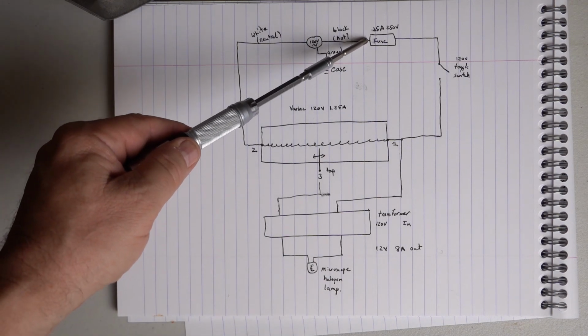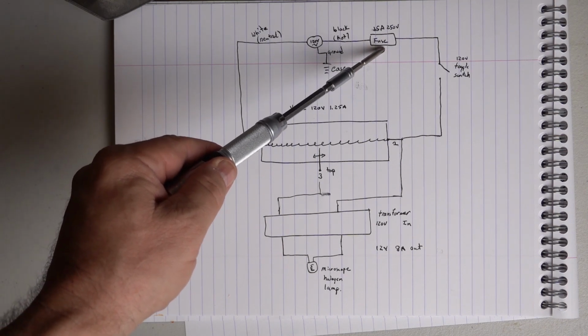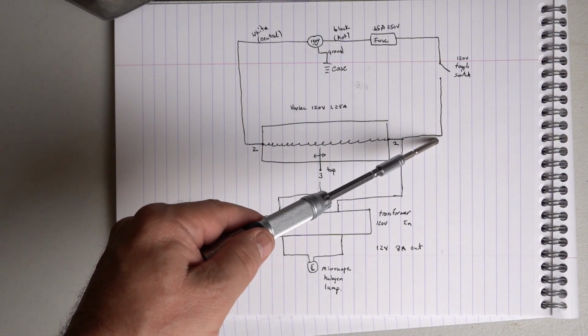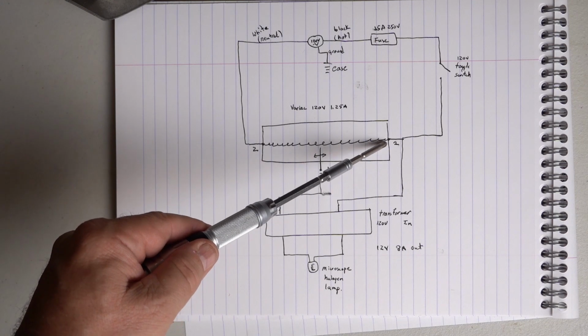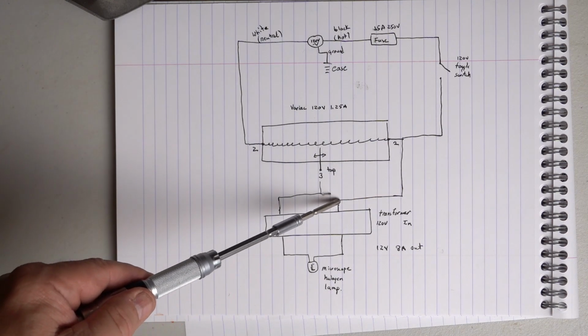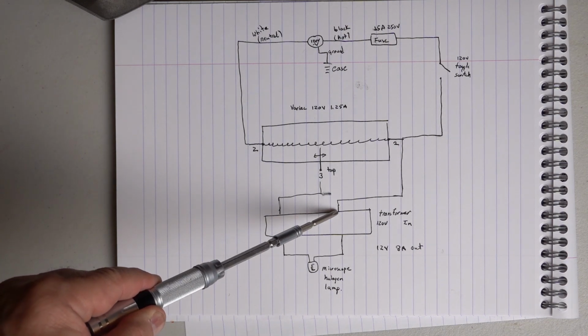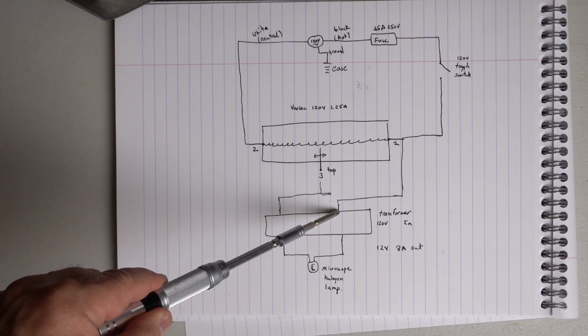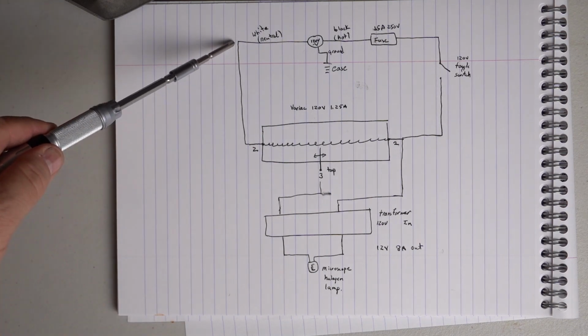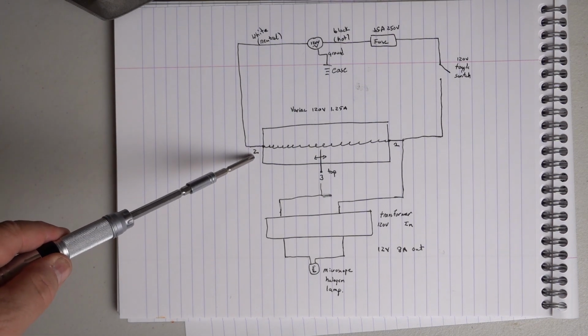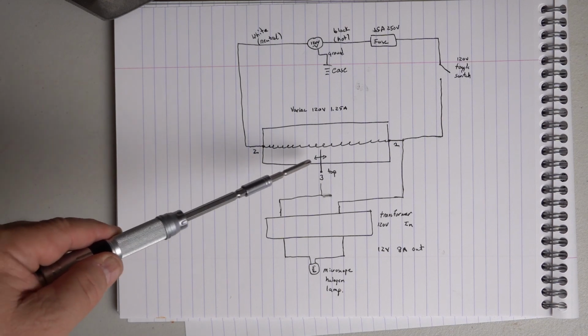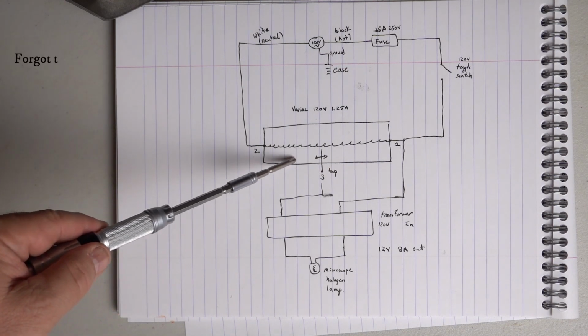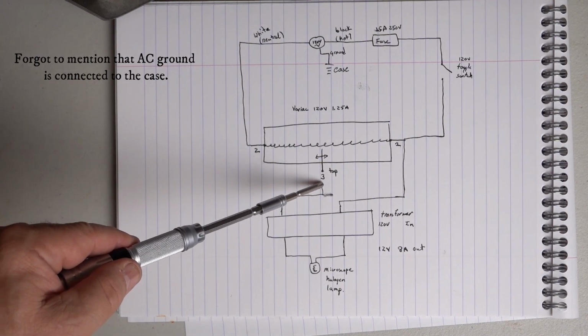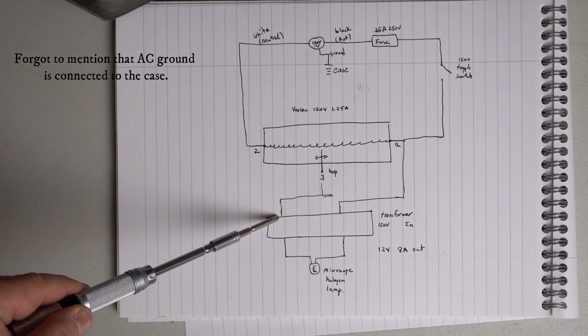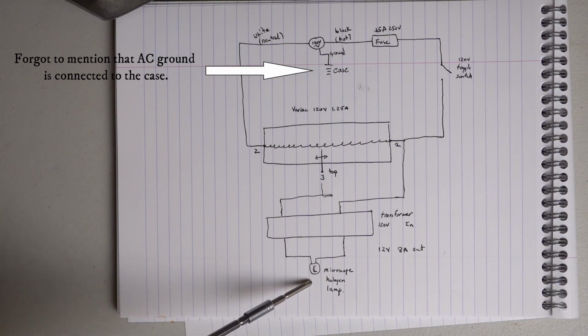The black hot lead off the wall goes through a 1.5 amp fuse and then to a toggle switch, and into pin 1 of the Variac, and also into one side of the 120 volt input on the transformer. The white neutral wire goes into pin 2 on the Variac, and pin 3 has the tap which picks the output voltage along the coil, and that goes into the other input on the transformer. The two outputs of the transformer go to the microscope halogen lamp house.